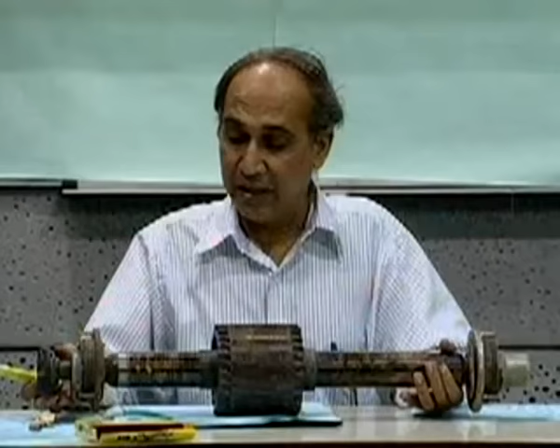While the stator core is fixed inside the frame, the rotor is mounted on the shaft, and you will see there are no brushes here. It's a brushless, rugged rotor, and there are two types of rotors. One is called a die-cast rotor, the other is called a brazed rotor. For a die-cast rotor, you pour liquid aluminum into the slots, cast it, and then machine it. For a brazed rotor, you put in copper bars, which are placed manually, and then brazing is done at the end rings. This is a typical squirrel cage.